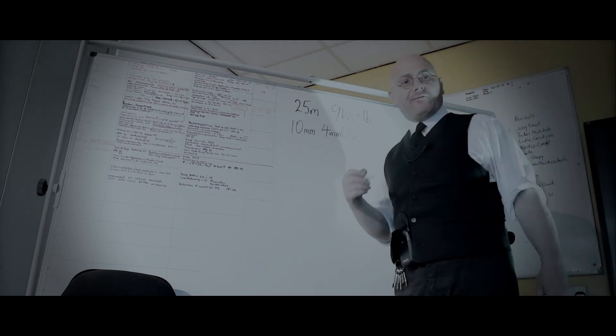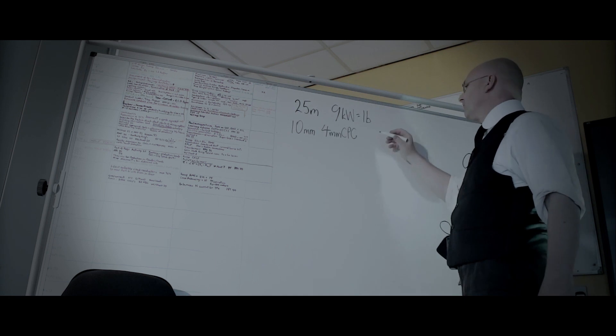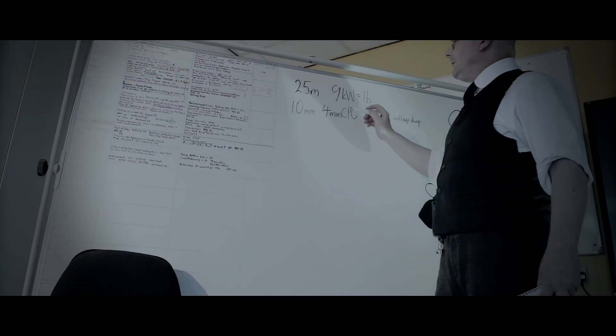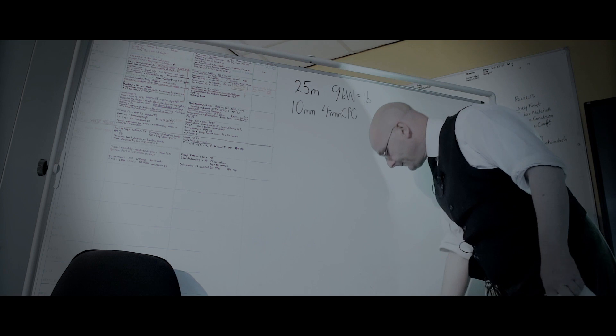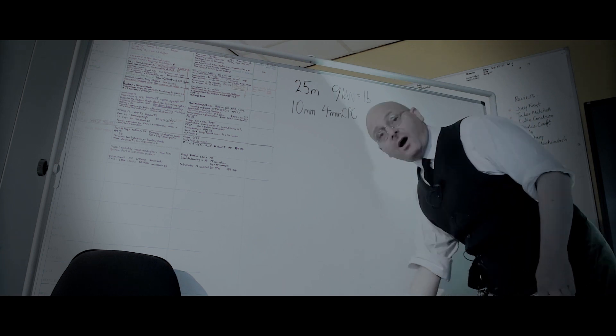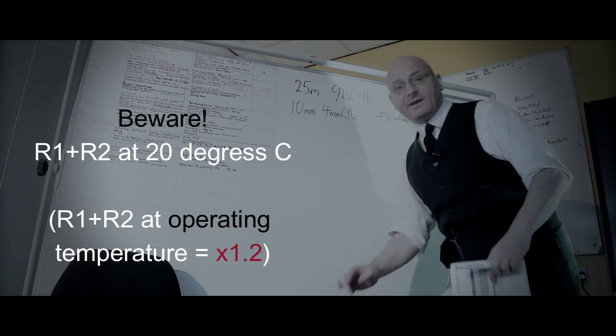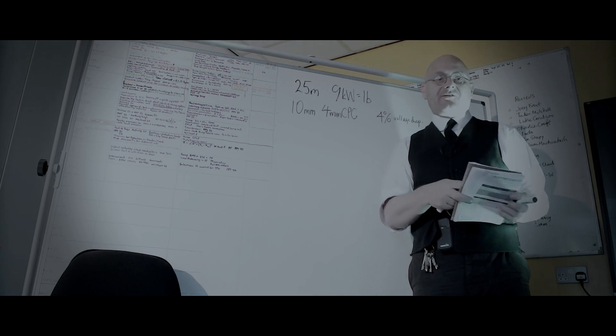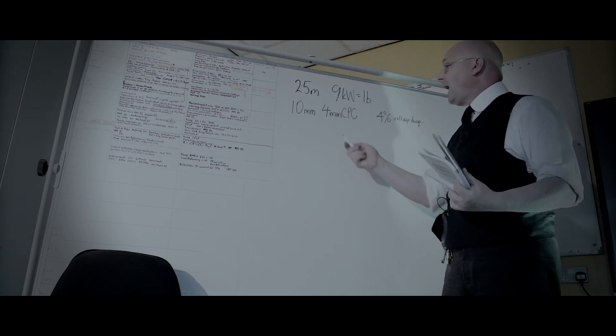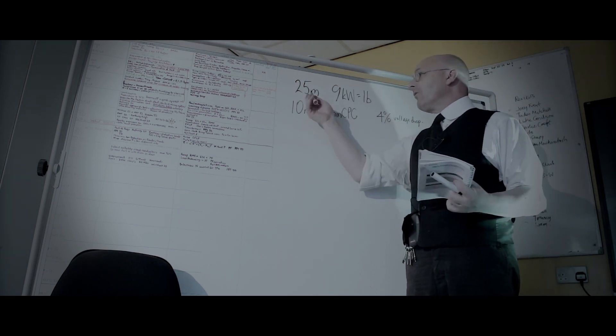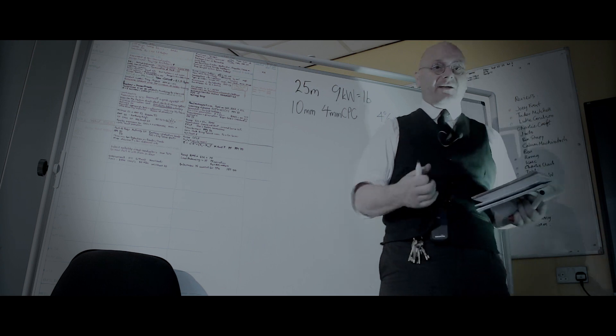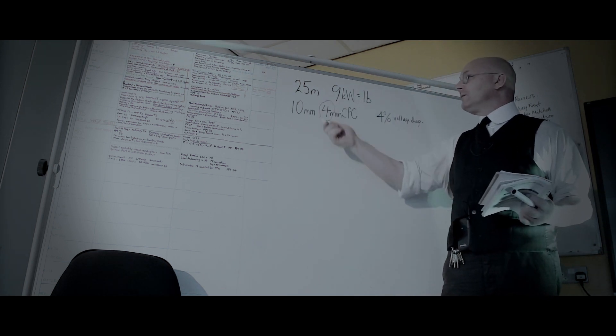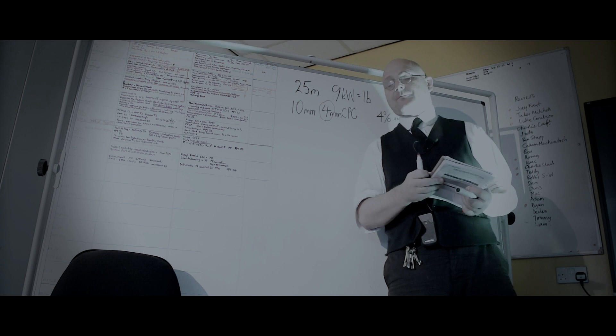Was there any other information we remembered about it? The voltage drop was something like 4%. What we need to work out now is our R1 and R2 of this circuit. Remember we're in the design stage and we need to work out how much current that CPC can take, and whether it's enough that it doesn't overheat.